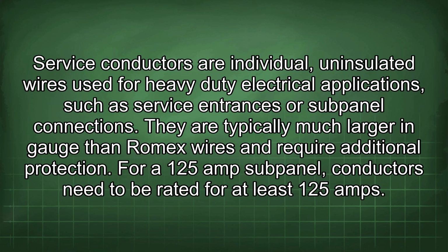Service conductors are individual, uninsulated wires used for heavy-duty electrical applications, such as service entrances or subpanel connections. They are typically much larger in gauge than Romex wires and require additional protection. For a 125 amp subpanel, conductors need to be rated for at least 125 amps.